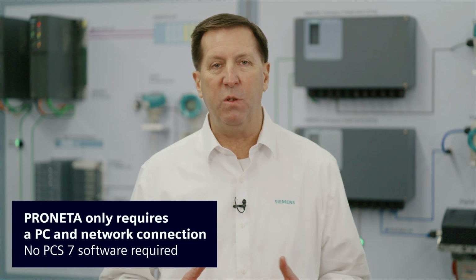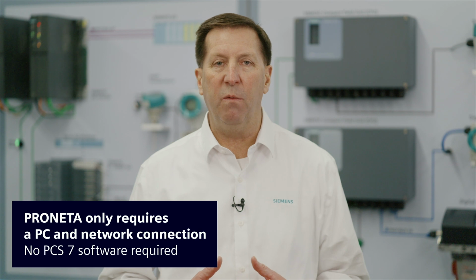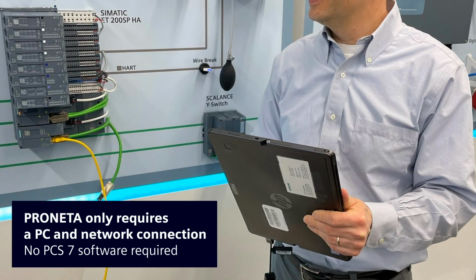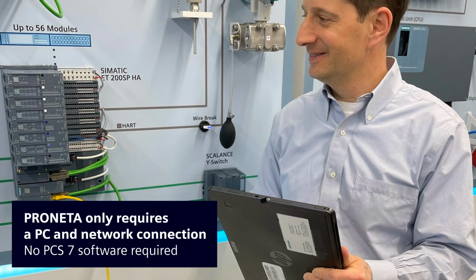During the development of an automation project, major components may be available for testing at different times. So how do you begin testing the I/O cabinets and wiring without the controllers and engineering station? The answer is PRONETA. PRONETA Basic is provided free of charge and allows the user to perform I/O network analysis and I/O channel testing. PRONETA does not require any PCS7 software and therefore can run in the absence of an engineering station. As a matter of fact, all you need is a PC and a network connection.